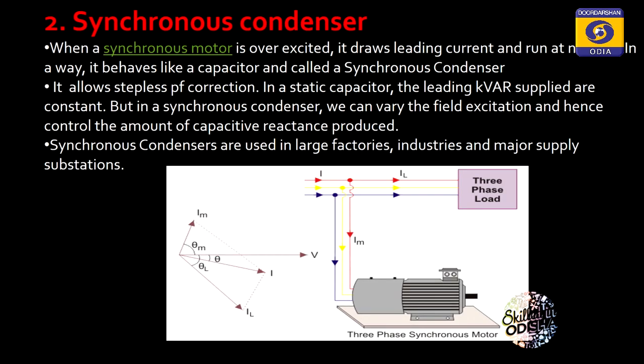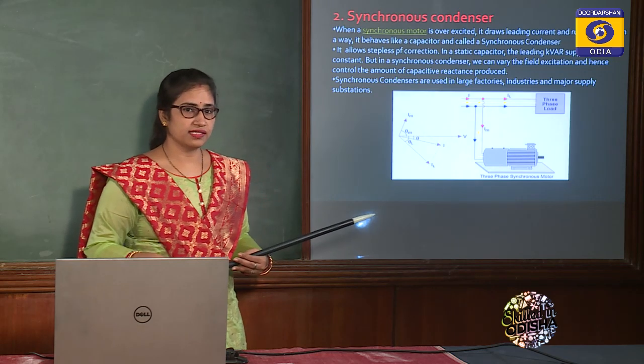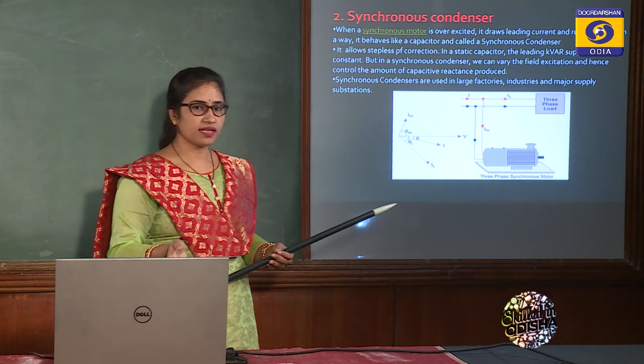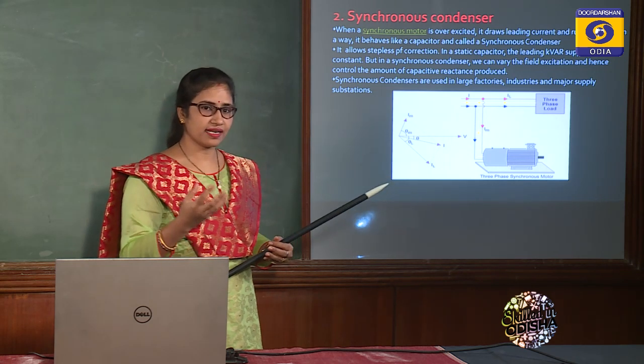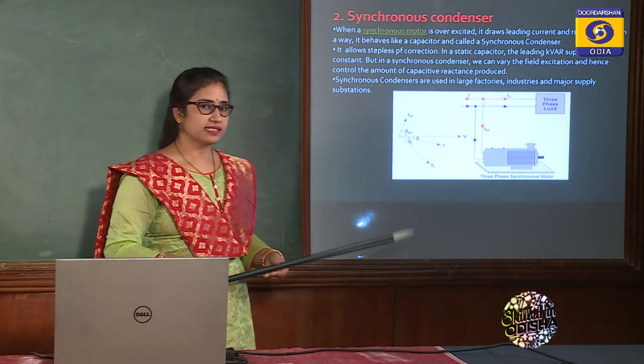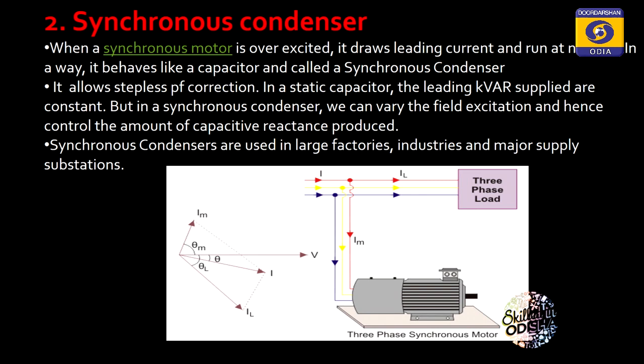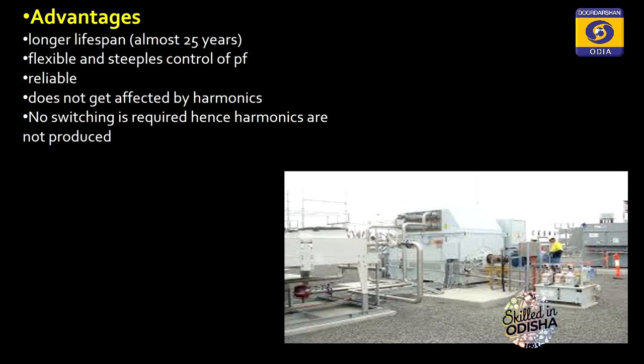The next method is a synchronous condenser. A synchronous condenser is nothing but a synchronous motor running in an overexcited state, at which time it acts as a capacitor. Advantages over a capacitor bank include a longer lifespan, flexible and stepless control of power factor, reliability, and no harmonic generation.